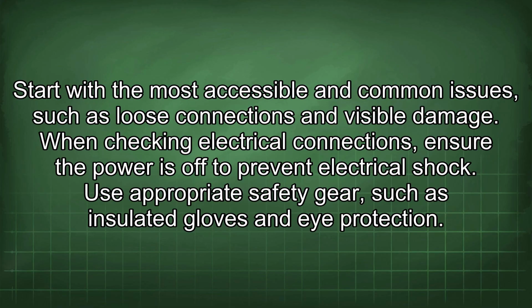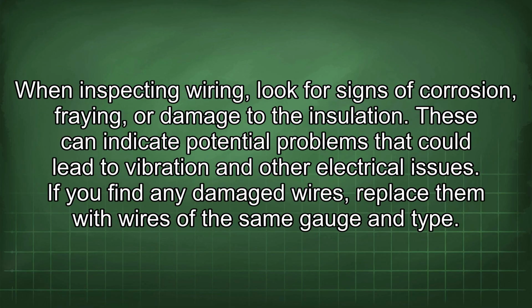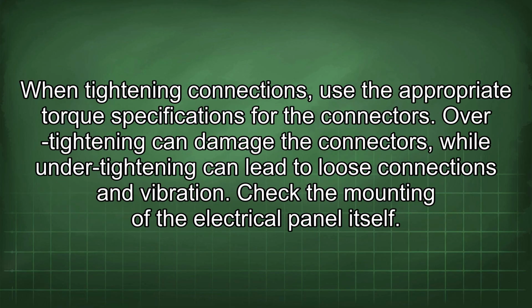When checking electrical connections, ensure the power is off to prevent electrical shock. Use appropriate safety gear such as insulated gloves and eye protection. When inspecting wiring, look for signs of corrosion, fraying, or damage to the insulation. These can indicate potential problems that could lead to vibration and other electrical issues. If you find any damaged wires, replace them with wires of the same gauge and type. When tightening connections, use the appropriate torque specifications for the connectors. Over-tightening can damage the connectors, while under-tightening can lead to loose connections and vibration.